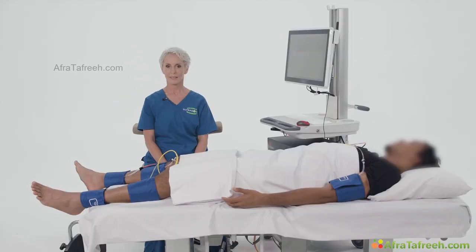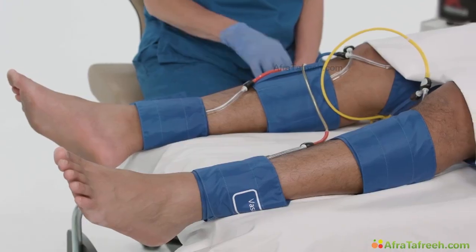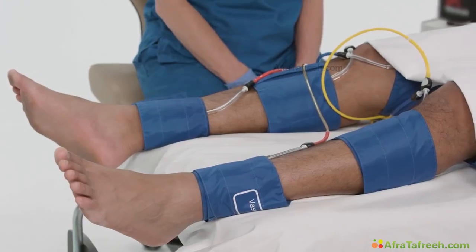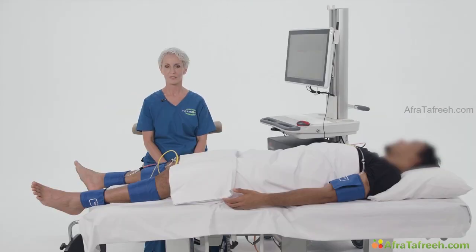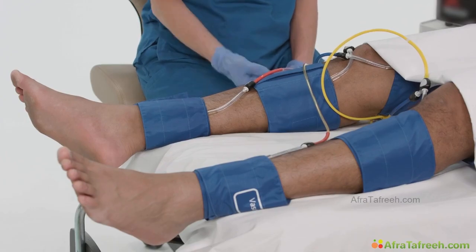Plethysmography measures changes in volume. This usually results from fluctuations in the amount of blood or air it contains. In this case, we're performing pulse volume recordings, or PVR. Air is inflated into the cuffs, somewhere around 60 millimeters of mercury. The plethysmography device senses changes in limb circumference with arterial pulsations as air in the cuff is compressed or displaced. The pressure transducer in the plethysmography device translates pulsations into graphically displayed waveforms. The waveform fluctuations correlate with changes in volume of blood within the segment under the limb of the cuff.